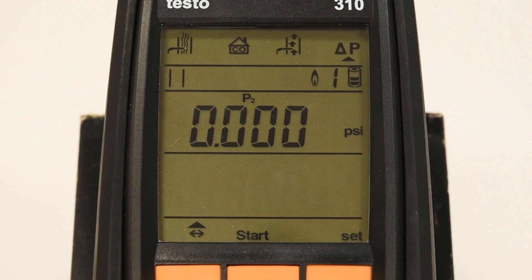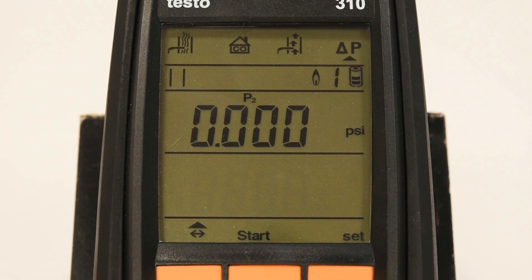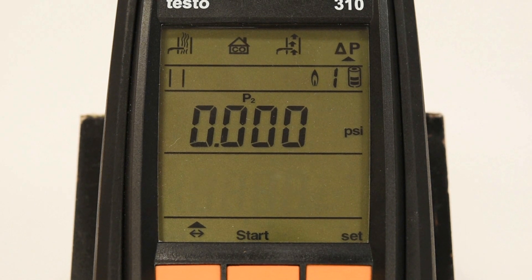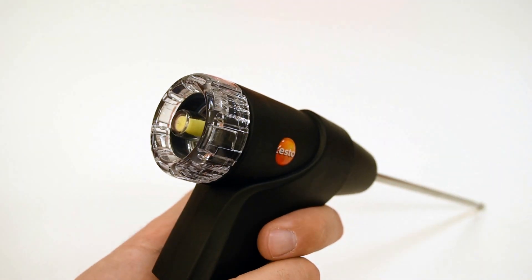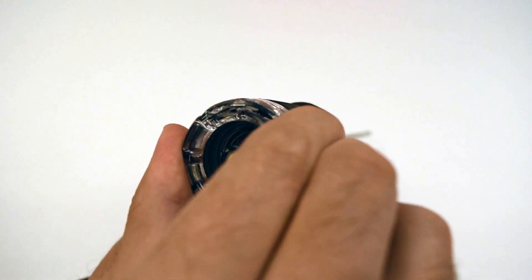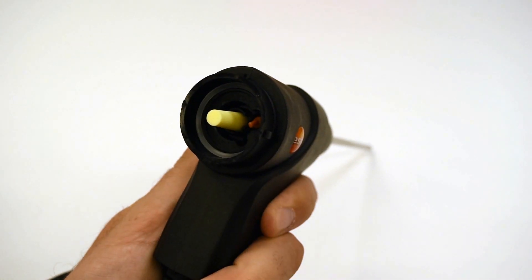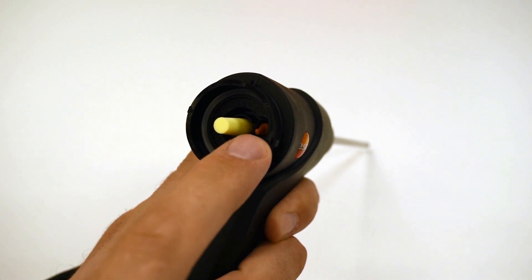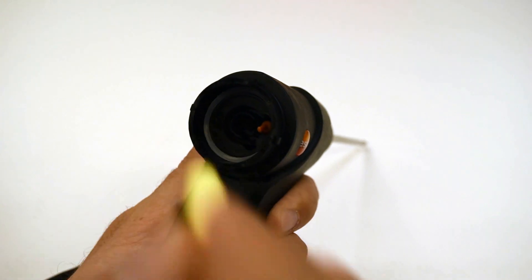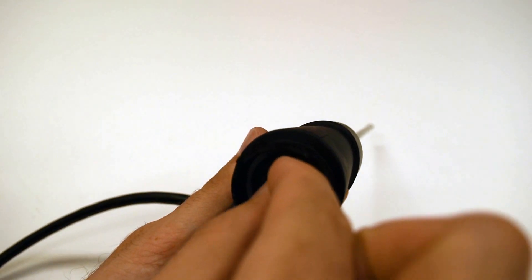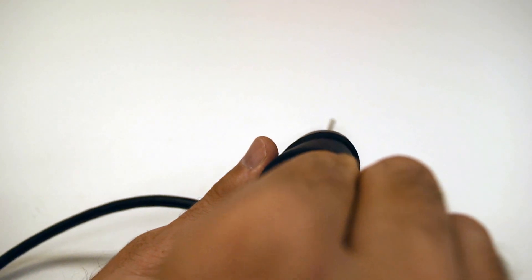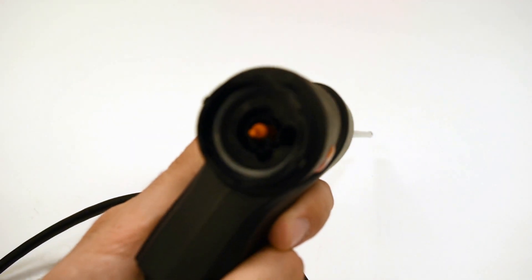When selecting differential pressure, you will see the term 'plug' appear on the screen. This indicates that you must remove the yellow cone filter in the back of your probe handle and replace the filter with the orange plug. To access the filter, rotate the plastic cover counterclockwise to unlock. You will find the orange plug stored conveniently in the space provided in the back of the probe handle. Remove the yellow cone filter, replace it with the orange plug, then put the plastic cap back on and rotate clockwise to lock it in place.